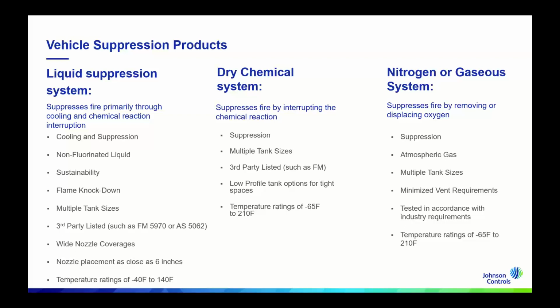On dry chemical systems, these systems suppress fire by interrupting the chemical reaction. With dry chemical systems, it's important to look for suppression capabilities, having multiple tank sizes to be able to have the right amount of dry chemical to suppress fire risks. Similar to liquid, right? Looking for those third-party listings. There are oftentimes environments and rating temperature requirements that would need to get down to -65, or in tight spaces, right? Like you might see in some underground mining where there's low profile options to be able to get those tanks in tight spaces.